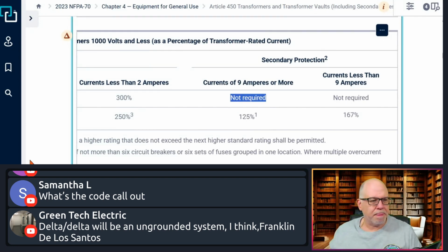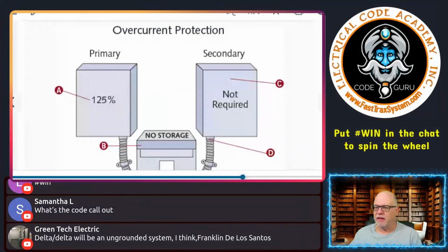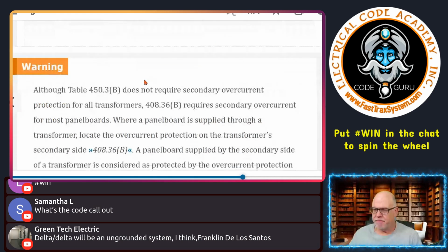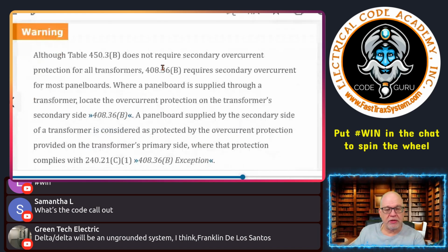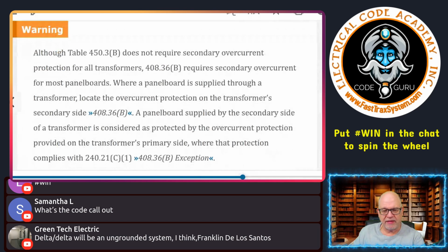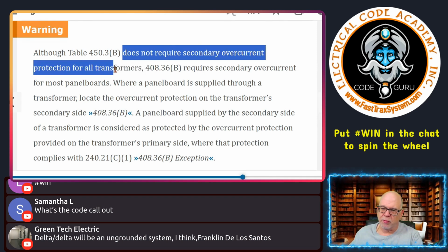typically what's going to happen is you're going to end up not doing it like this. You're going to be terminating it into a panelboard that's inside of an enclosure. And when that scenario happens, you have to remember that you also have requirements to protect that panelboard. They may or may not also be considered protecting the transformer, because now I'm terminating it into an overcurrent protective device.